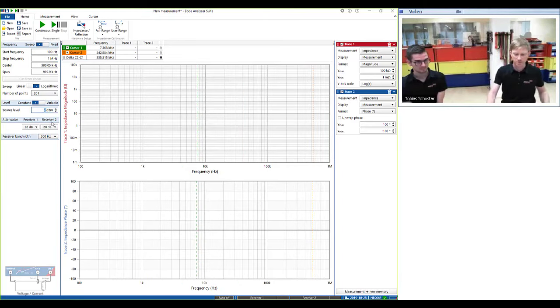Then the source level. Here we can use the maximum power because the current injector will then give us roughly 20 milliamps modulating AC current. That's no problem for the 1 amp regulator system. I'm going to reduce the attenuators. I don't think that we need them, otherwise we can increase them again, and I set the receiver bandwidth to 100 Hz. And then I think we're done, and I start the measurement.